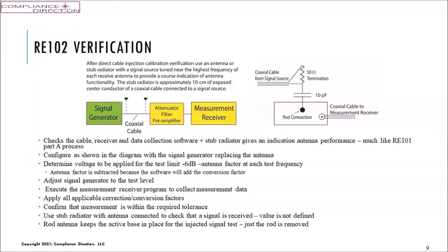In the commercial world, it's done that way, where you set your antenna and you always need to get the same answers. Now, the rod antenna comes into being here and is a little bit more difficult or different. So in that case, we would take away the rod and hook up a 10 picofarad coupling network into where the rod antenna goes. And we would inject the signal across the 50 ohm termination to develop a voltage for the high impedance rod input. And that measurement should be present.